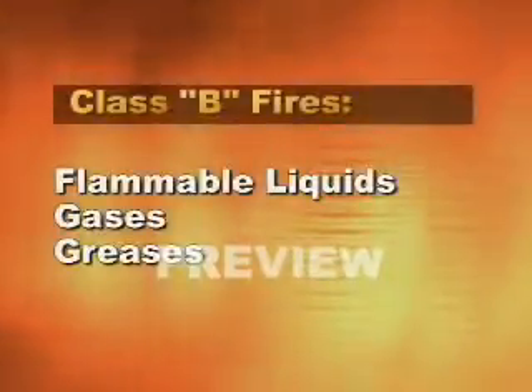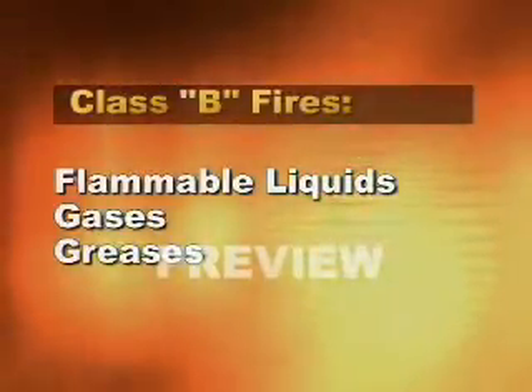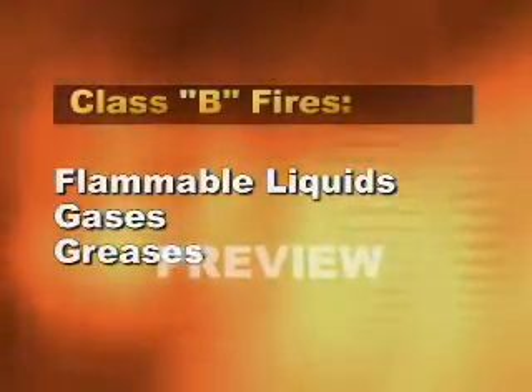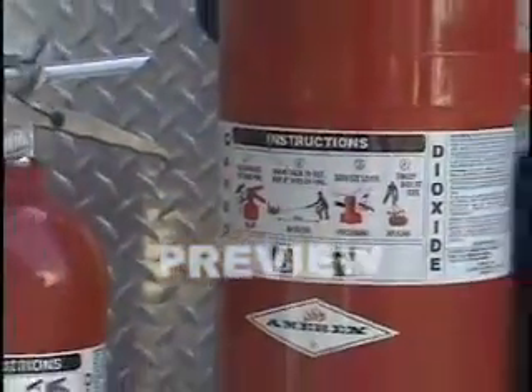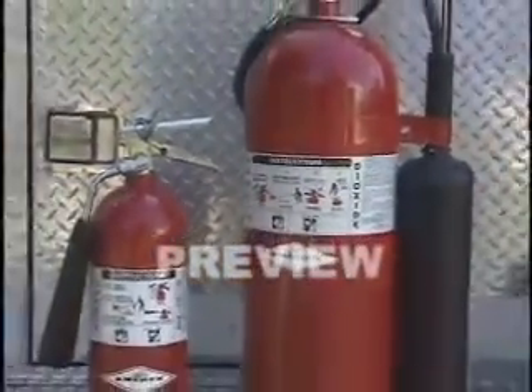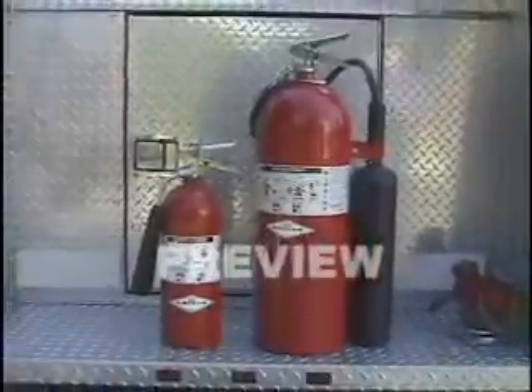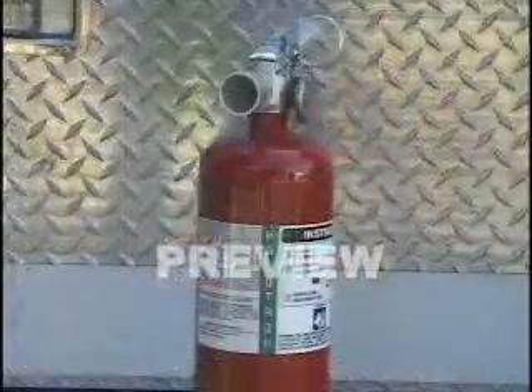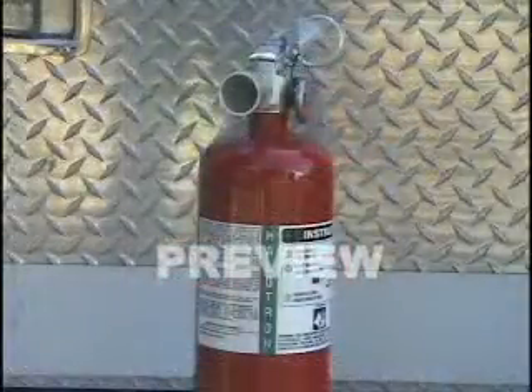Class B. Flammable liquids, gases, and greases create Class B fires. The correct extinguishers to use on Class B fires are foam, carbon dioxide, or dry chemical. Halogenated agent extinguishers can also be used.